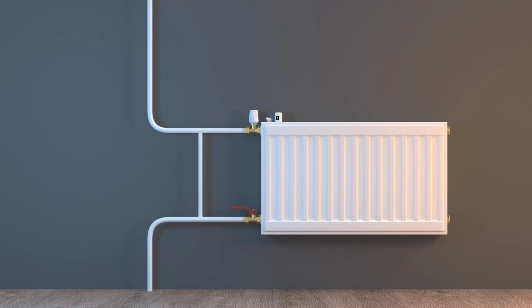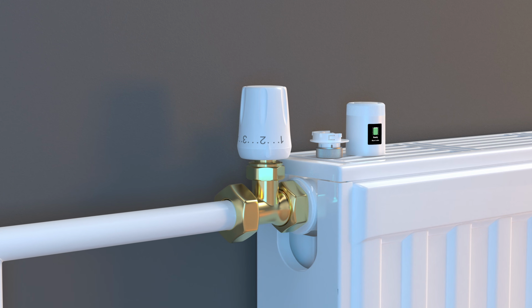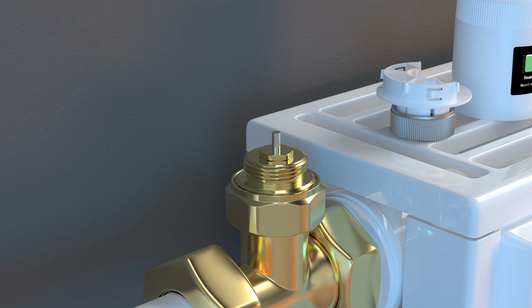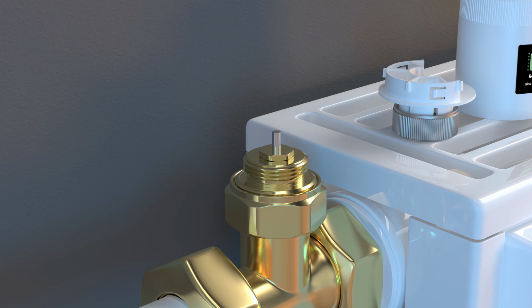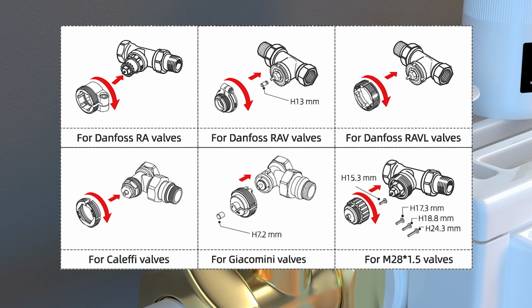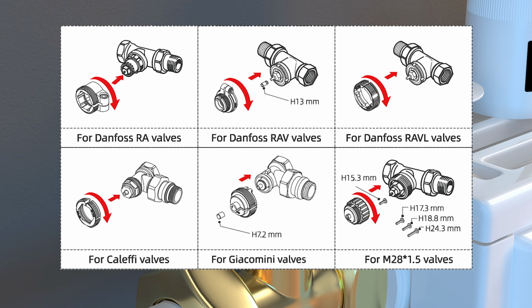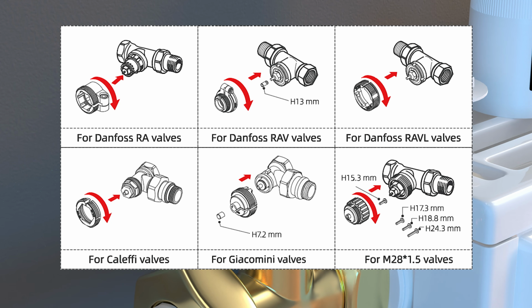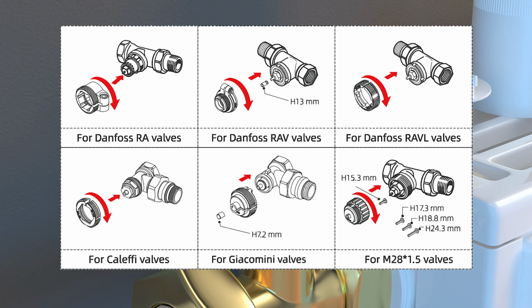First, remove your existing thermostatic radiator valve head. Check whether your valve connection is M30 by 1.5 millimeters. If your valve connection is not M30 by 1.5 millimeters, install the appropriate adapter onto the valve first. For more information, please refer to the quick guide and user manual.